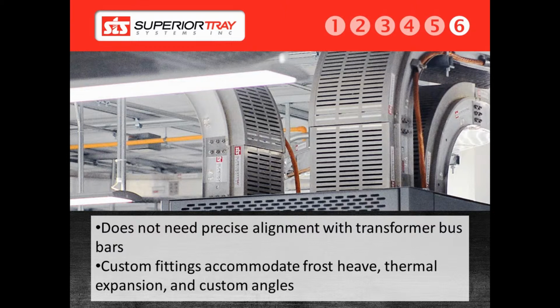We do not pre-cut our cables before shipping them to the customer. All of our cables are sent on reels along with the rest of the SuperiorBus system. In the event that there is a change to the cable bus, we can reconfigure the cut lengths and send a cutting list so that the customer can effectively cut and install the cable with minimal waste. If the job site has changed drastically enough that it requires more cable, we will send the extra cable along with a cut list to use the previously ordered cable as effectively as possible.